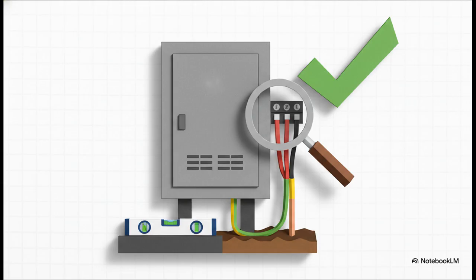First, the mechanical side. Is that low voltage panel sitting perfectly level on a solid foundation? Then, the electrical checks. Are the LV cable terminations completely tight? Next, we verify the earthing. Is the LV neutral grounded? Are the meter boxes mounted securely and at the right height? Have we verified the customer ground bonding? This is your absolute final quality control checkpoint before you even think about introducing power.